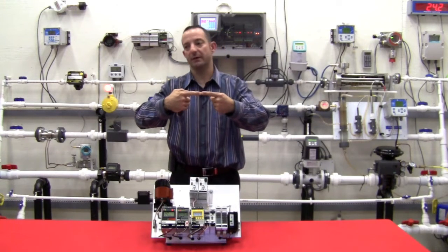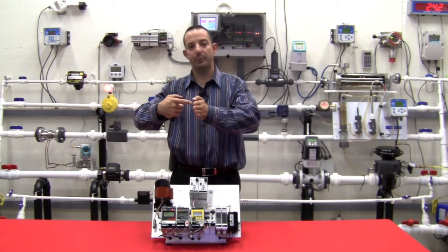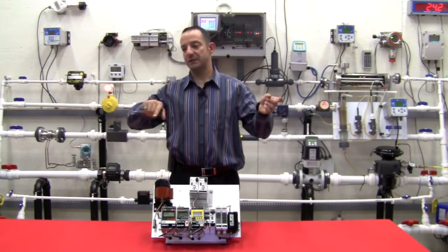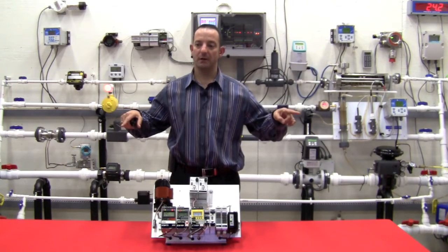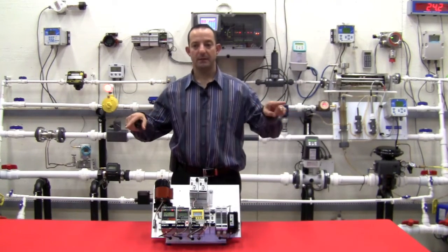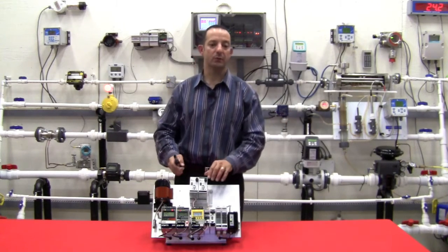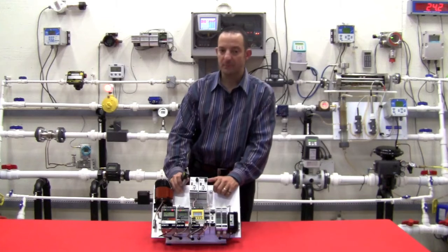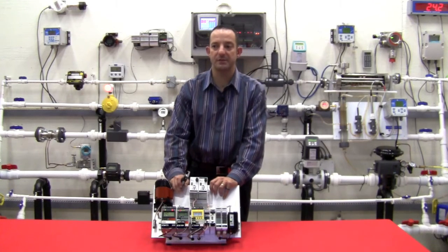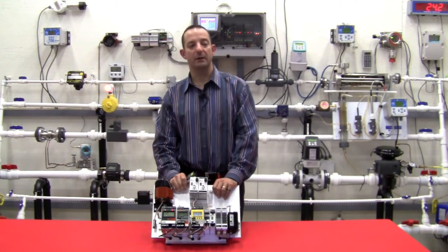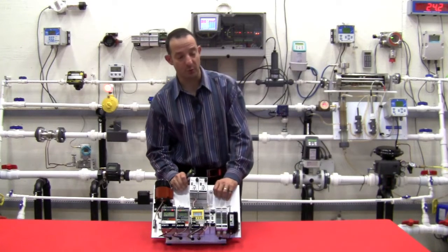So what an isolator does is it splits that loop in 2 and allows each to source the current in each half of the installation, and the output current is always equal to the input current. That is also covered in the isolators and ground loops and causes and cures brochure.